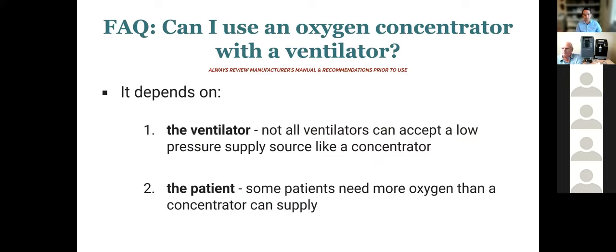Okay, so a common question that comes up, can I use an oxygen concentrator with a ventilator? And it depends. Most ventilators, that is not the case. Most ICU ventilators will require a high pressure oxygen source, and these portable oxygen concentrators do not produce oxygen at 50 PSI, 3.5 bar, they're usually closer to 20 PSI or less. But some ventilators can.